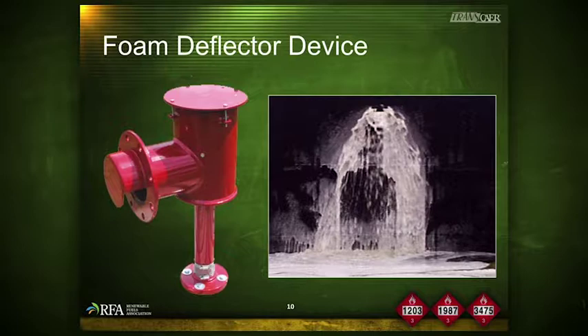Before the fire or foam attack can begin on a tank, responders need to calculate the available space within the tank. Working with facility operators to calculate the available space in gallons will allow responders to know if the product needs to be removed from the tank before operations can begin, or allow the product to burn off to reduce product in the tank. Fire operations have to account for finished foam going into the tank so as to not overflow contents. Expansion needs to be taken into consideration.